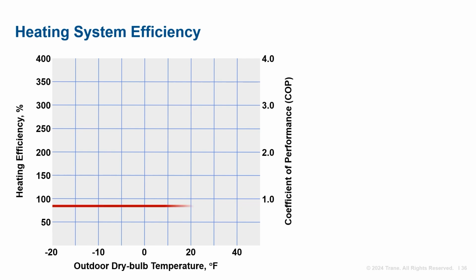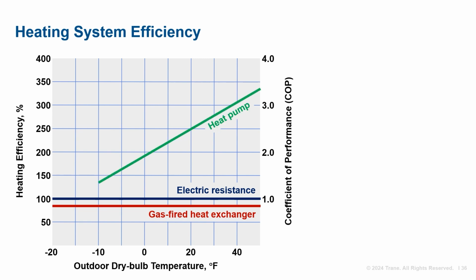Today, gas-fired heat exchangers are required to be 81% efficient, which means for every 100 BTUs of gas consumed, we get 81 BTUs of heat. Electric resistance heating is 100% efficient. All energy in becomes heat. This is a COP of 1. But heat pump heat output is a function of ambient conditions. How much heat can be removed from the ambient air? It is not constant. And we can see that as ambient temperatures decrease, the efficiency decreases.